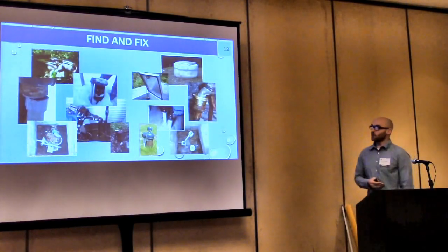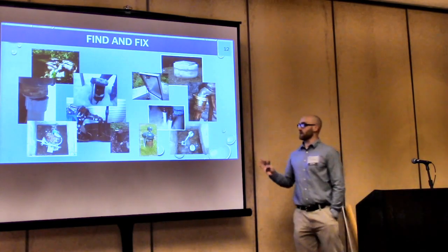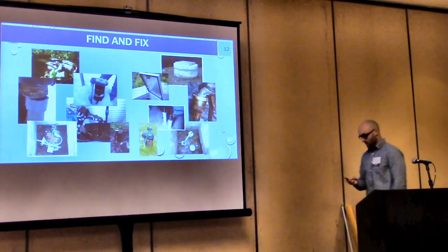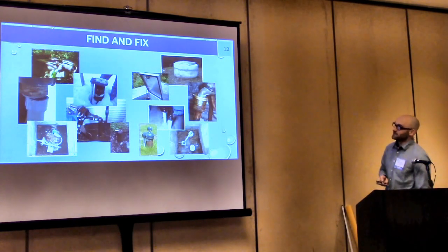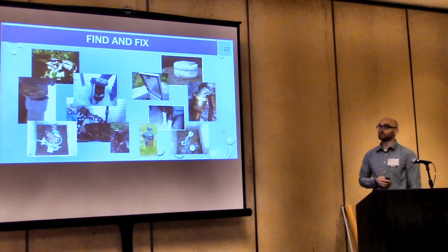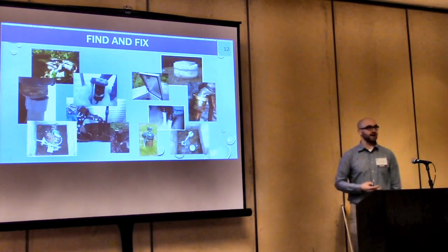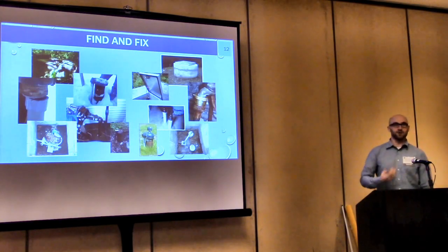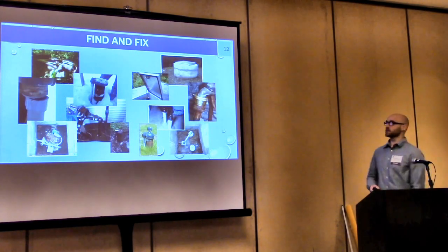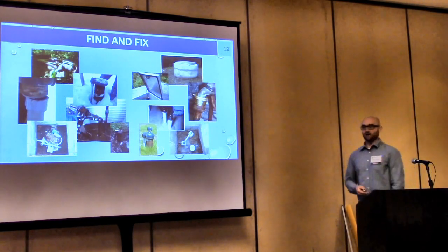So the ultimate goal of the RTCR is to go from left to right in these pictures. You can see up here, wow, I'm shaking, huh? There's a spring box in the woods with a little plug type cover. Not ideal. Rain, surface water, insects, small rodents, things like that can get into the system. Not sanitary construction.